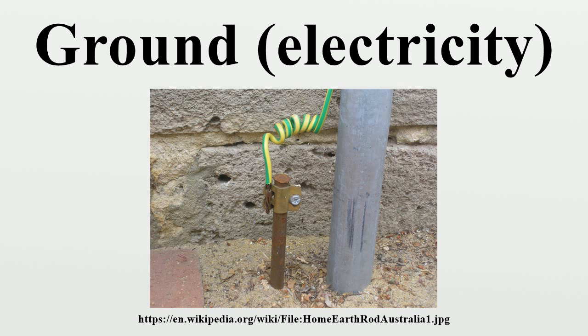Bonding. Strictly speaking, the terms grounding or earthing are meant to refer to an electrical connection to ground, earth. Bonding is the practice of intentionally electrically connecting metallic items not designed to carry electricity. This brings all the bonded items to the same electrical potential as a protection from electrical shock. The bonded items can then be connected to ground to bring them to earth potential.